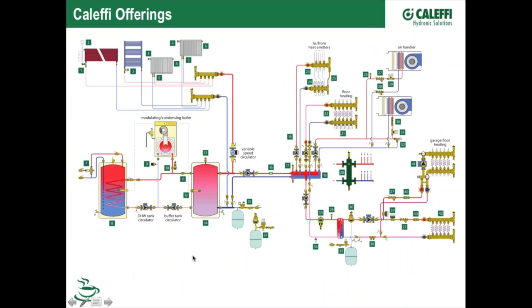Well, as far as pumping into a boiler, a lot of the new ModCon boilers that have tight heat exchangers, the manufacturers suggest that you pump into it so that the boiler sees that increase in the delta P when the pump starts up. So what we want to do is pump away from the point of no pressure change, if at all possible. The point of no pressure change is where we connect the expansion tank in the system. So in this picture here, you can see we've attached the expansion tank. We've established our point of no pressure change right here.